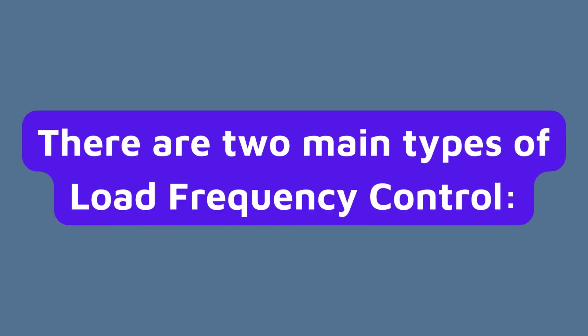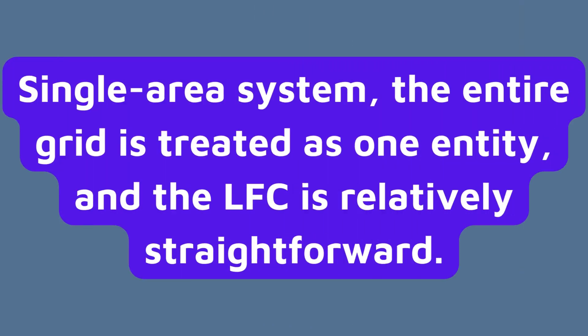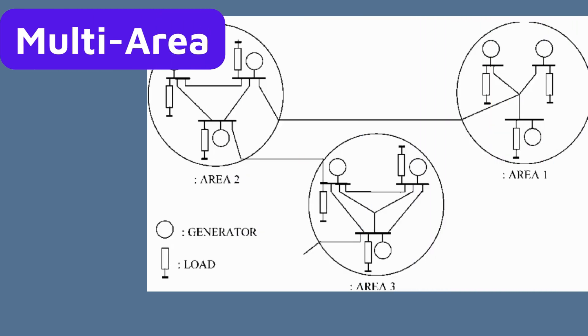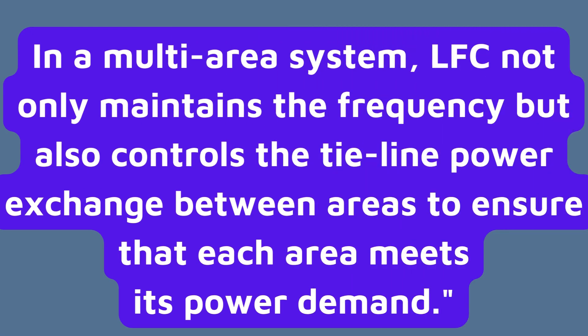There are two main types of load frequency control: single area and multi-area. In a single area system, the entire grid is treated as one entity, and the LFC is relatively straightforward. However, in a multi-area system, which is more common in interconnected power grids, LFC must consider the frequency and power interchange between different areas. In a multi-area system, LFC not only maintains the frequency, but also controls the tie-line power exchange between areas to ensure that each area meets its power demand.